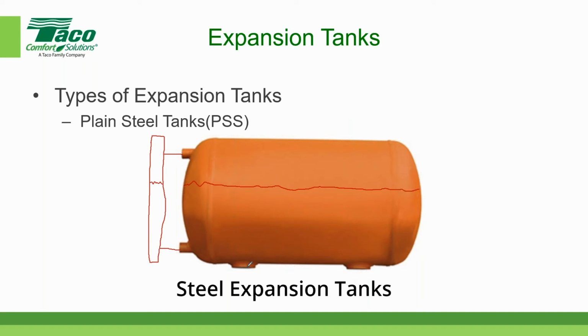There are two other connections at the bottom. One typically is connected to the system. Also, I'll just break the pipe here and show it connected to the system. And the other connection is typically connected to some kind of drain valve or blowdown valve. And that goes usually to a floor drain over here. And that's it. That's all there is to a plain steel tank. There's no bladder physically inside the tank. Essentially, it's just an empty container. Okay, so let's go on to the next category.